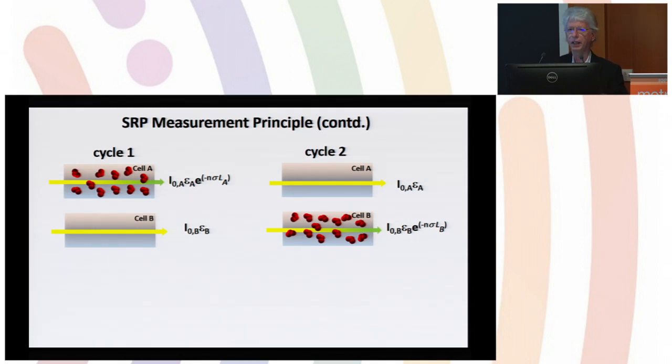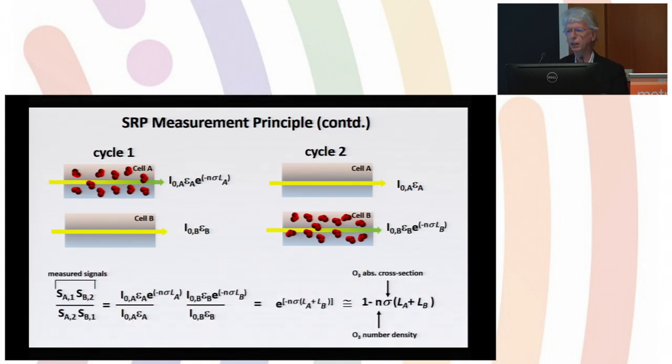The actual SRP instruments involve two cells in parallel in an anti-symmetric fashion where in cycle one you fill one with ozone, the other one is just air, then you repeat cycle two and invert the sample gas. You have a common lamp and common detector. If you're doing this ratioing technique, all the common factors of transmission and reflection cancel out.